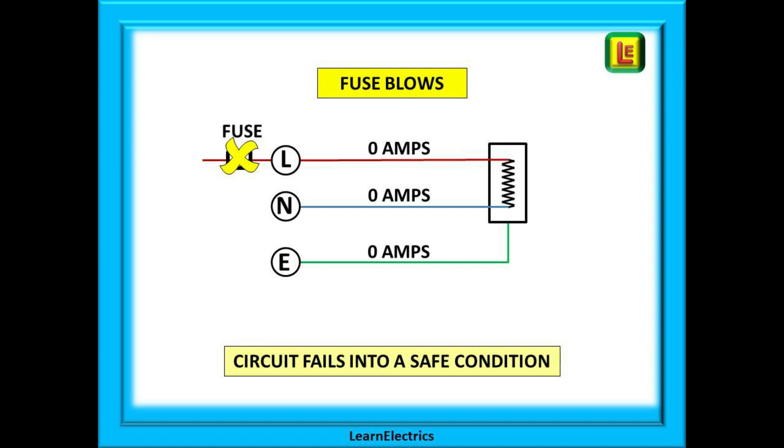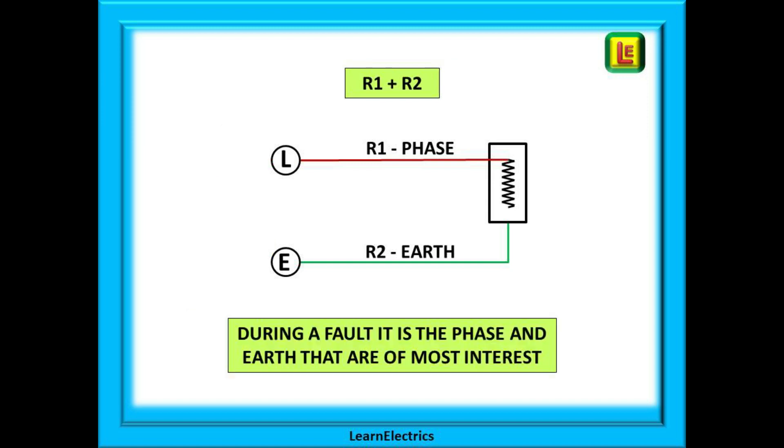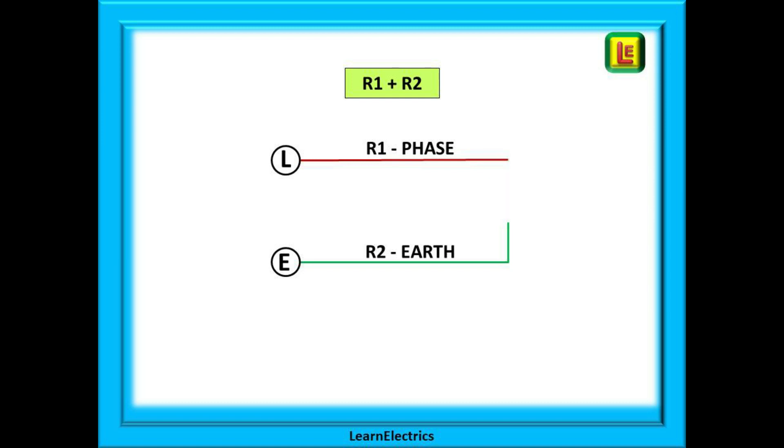During a fault the neutral plays very little part in what is happening, so let us remove the neutral on this drawing. We are left with just R1 the phase wire and R2 the earth wire, and it is the massive currents that are flowing around R1 and R2 that cause the fuse to blow or the breaker to trip. Therefore during a fault it is the phase and earth that are of most interest. We want to know what the resistance is of these two wires as resistance is the thing that will reduce the amount of current flowing. Resistance is the enemy.